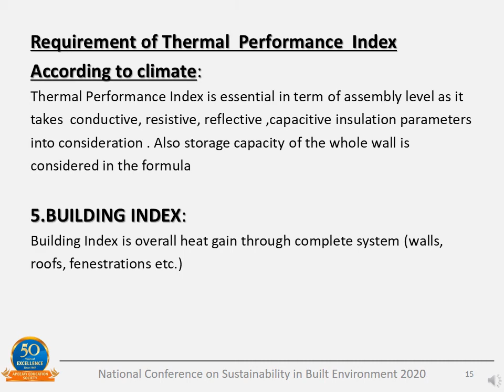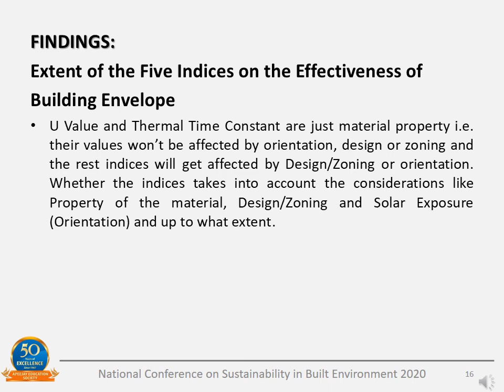So from this, findings are derived on the extent of the effect of the 5 indices on the effectiveness of the building envelope. U value and thermal time constant are just material properties. Their values won't be affected by orientation or zoning. But yes, the thermal time constant depends on the material and the assembly or layering of the material. The rest of the 3 indices will be affected by zoning, orientation and the kind of material taken.